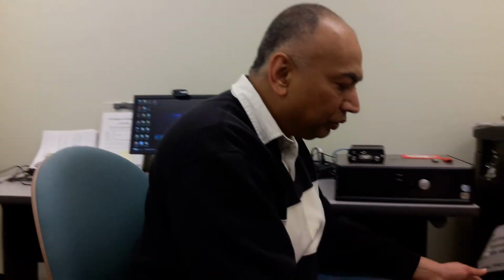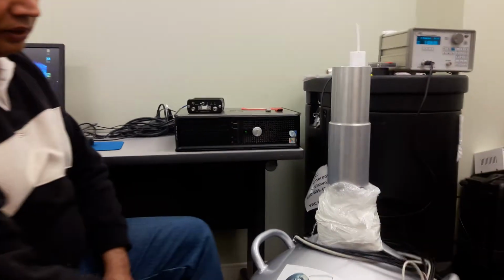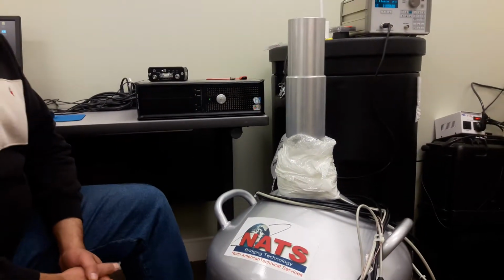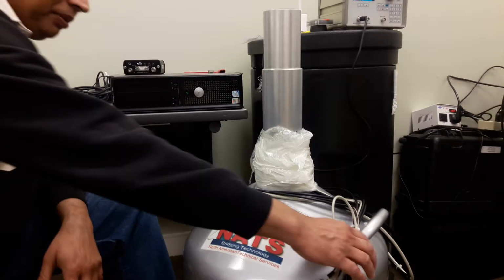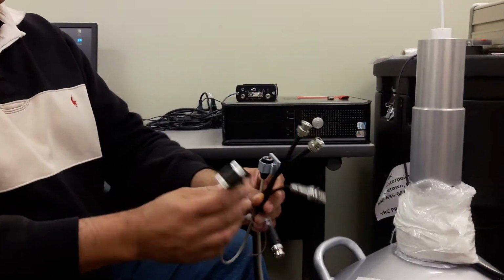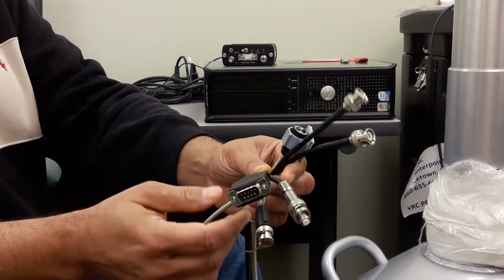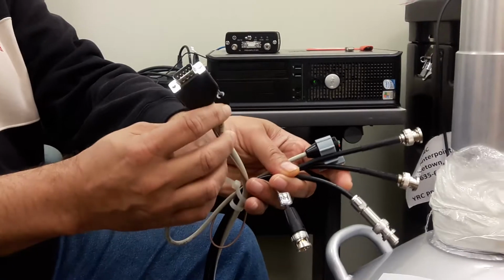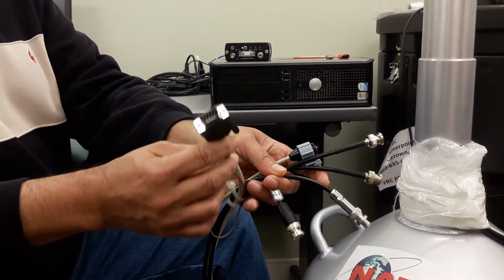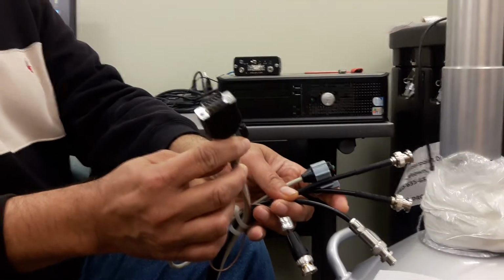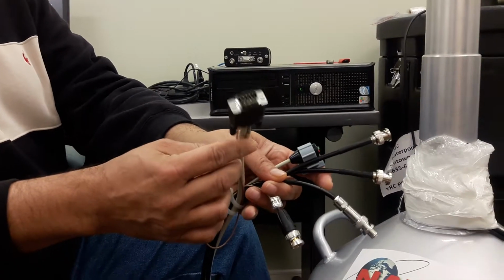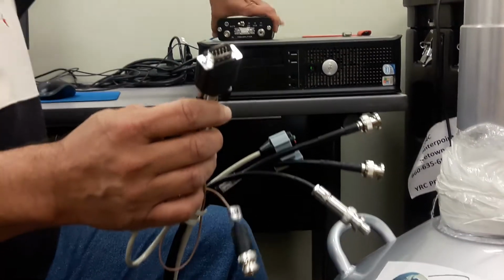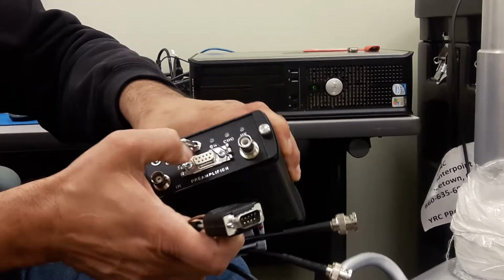First of all, I will explain to you the germanium detector. This is a coaxial germanium detector which is liquid nitrogen cooled. It's a high resolution germanium detector and it comes already with some cables and connectors. I want to make sure that you understand the various cables. The first thing that you will see is this big preamp type cable, which is a 9-pin DB connector. This cable here is used to connect to the back part of most MCAs, which is called the preamp power.